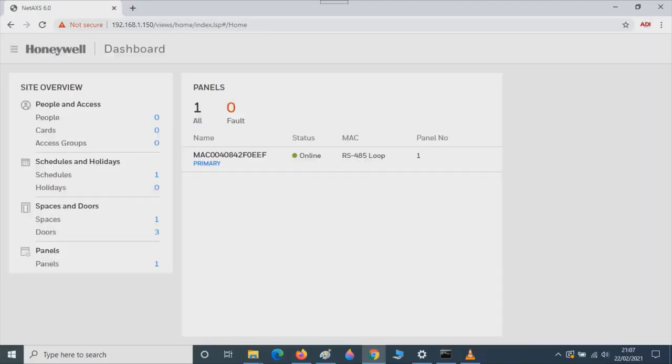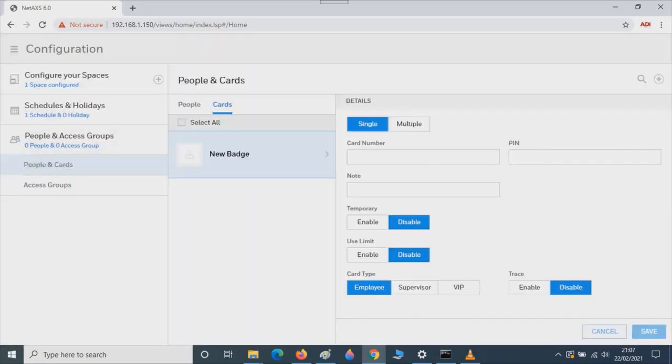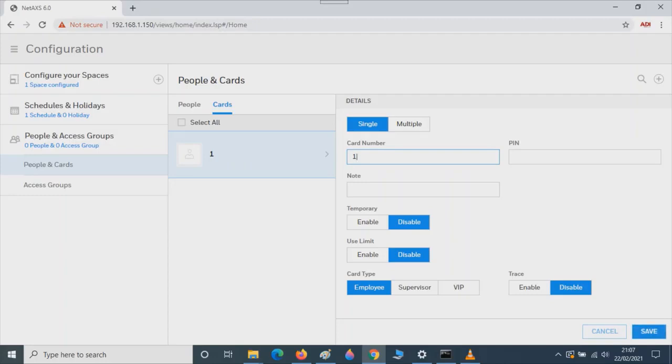Adding a card. We're now going to add a card and a username. Then we're going to add it to a 24 hour time zone. This 24 hour time zone will also give access to all doors. Let's go to the menu, then to Dashboard. Then we're going to click on Cards. Add a card. Type in the card number that's normally printed on the front of all Honeywell cards. In this case it's an eight digit number. Once you've added the card, press Save.